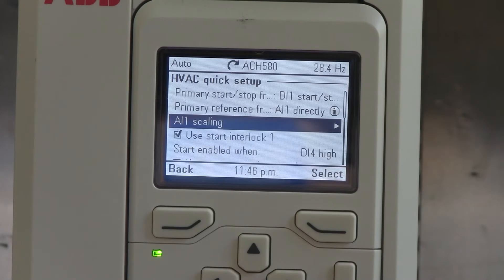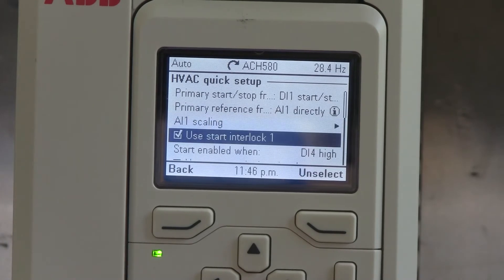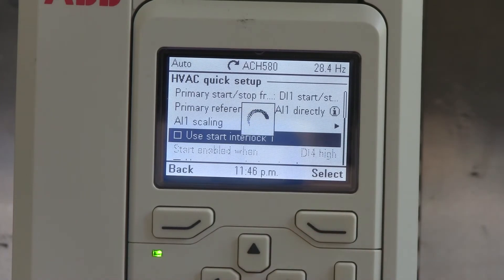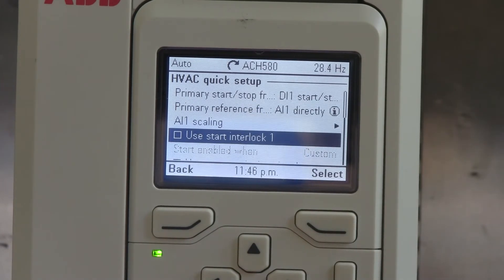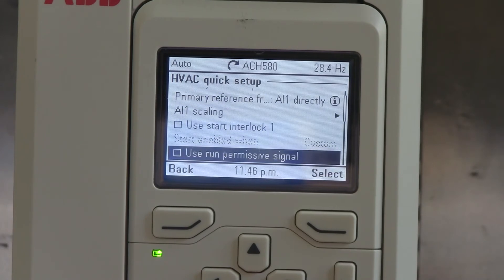After that's done, you can decide whether you want to use a start interlock. Right now it's programmed for a start interlock on DI4. I have a switch made already, so it's not an alarm. But if you wanted to change that, you could hit unselect and it will disable it for you. If you hit the down arrow again, you'll run into a run permissive signal. This is similar to a run enable where that needs to be made before the drive will run.